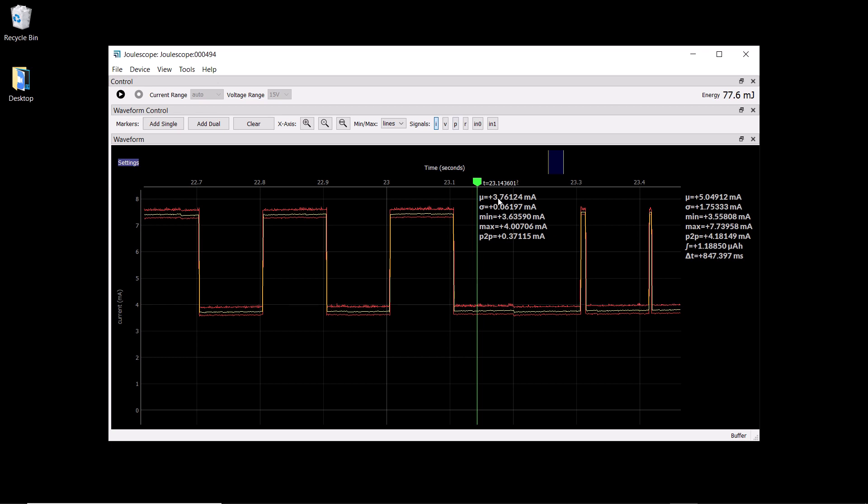The single marker displays statistics of mean, standard deviation, min, max, and peak-to-peak, just like the multimeter view. We also see the statistics displayed over the full window that's observed here, and it also includes our integration in amp hours.